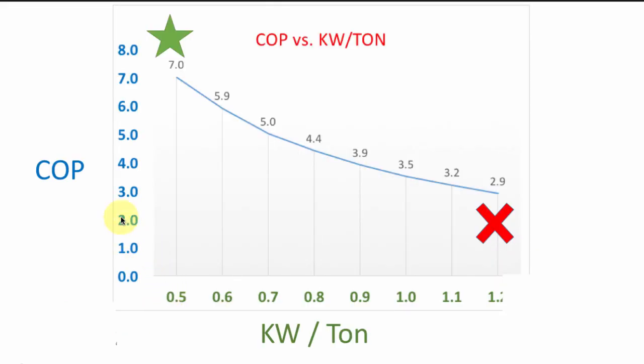Here's the same answer shown on a different type of chart. For KW per ton, you want a small number because that means it takes less power — less KW in — to produce a ton of cooling. For COP, you want a large number, which means more efficient equipment.